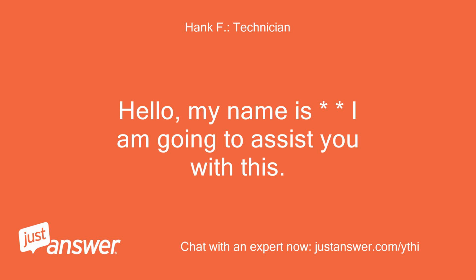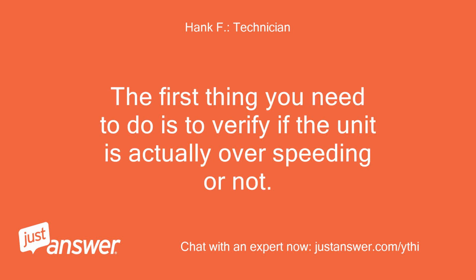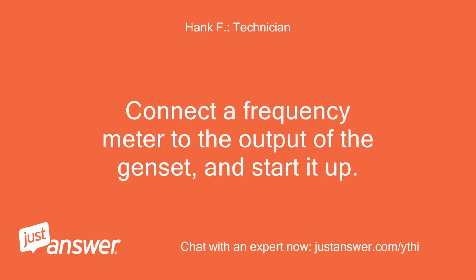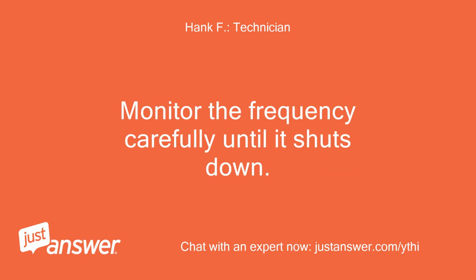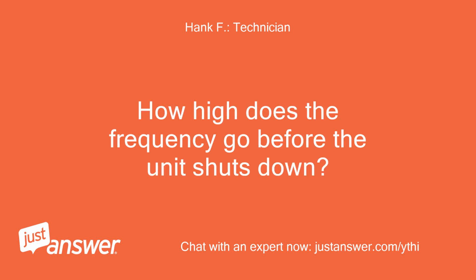Hello, my name is. I am going to assist you with this. The first thing you need to do is to verify if the unit is actually overspeeding or not. Connect a frequency meter to the output of the genset and start it up. Monitor the frequency carefully until it shuts down. How high does the frequency go before the unit shuts down?